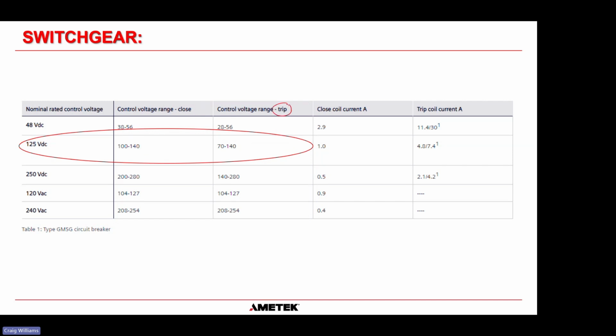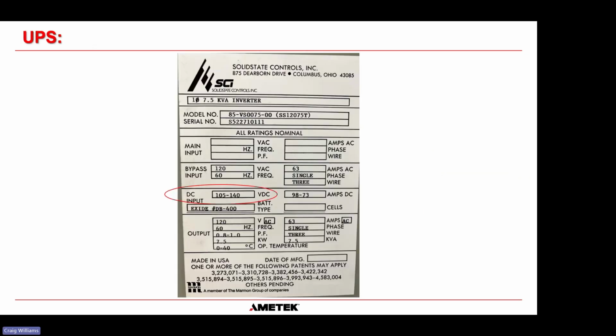And for the trip circuit, they're saying you can go down as low as 70 volts, okay? But once again, they're saying you may damage components if you go above the 140 volts. So that's the balance that you've got to get right. You've got to choose the right battery that the charger is going to charge between, for this system here, 100 to 140 volts without damaging the system. That's the trade-offs you have to have.